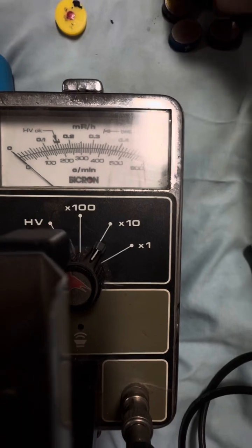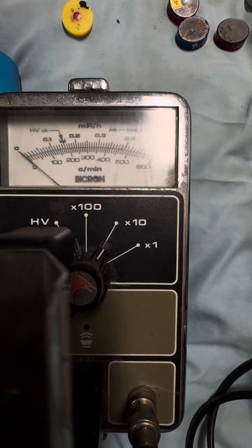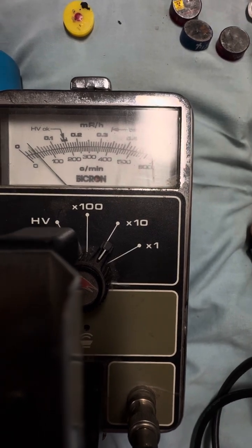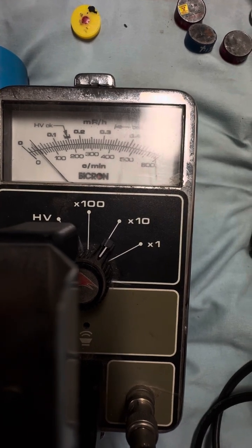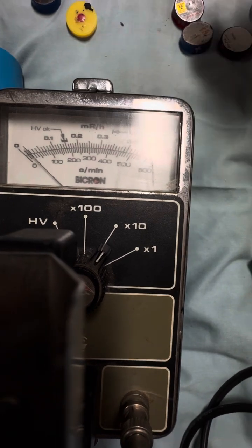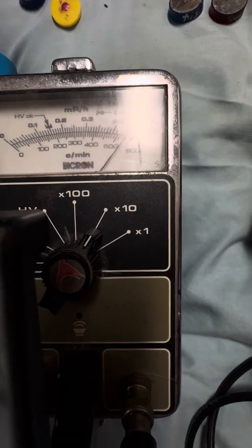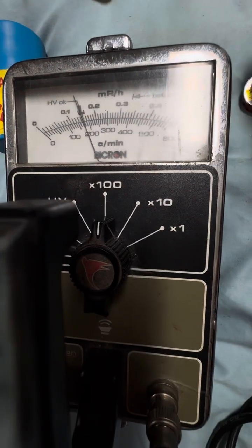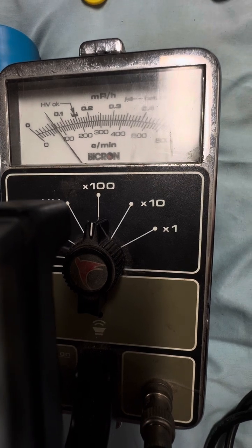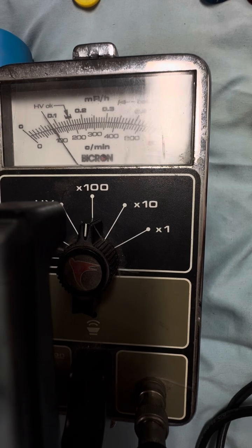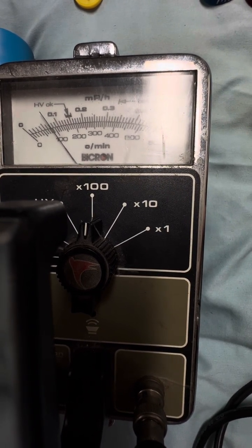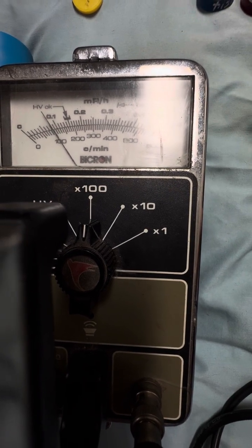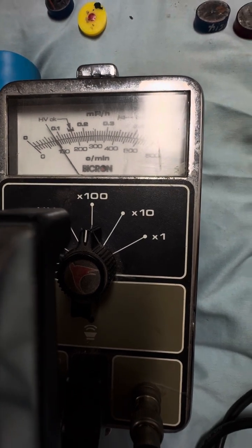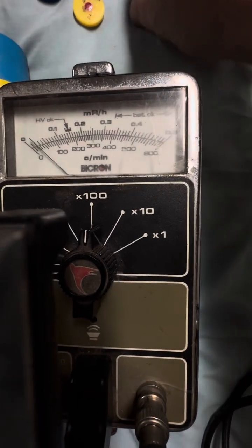So let's go next with some Cobalt 60. Right here. It has decayed substantially, this source, so it's not very strong. But, as you can see, it's still deflecting. Let's go with some strontium 90, which is a beta only emitter. That's a pretty strong one. So yeah, maxes out the X10. Let's do it on X100. So we are getting approximately 90 or 9,000 counts per minute with that beta only strontium 90 source placed directly up to the probe.